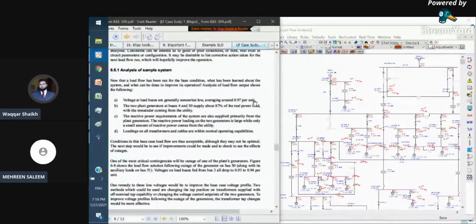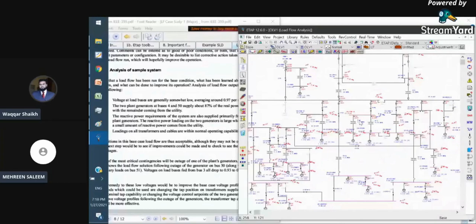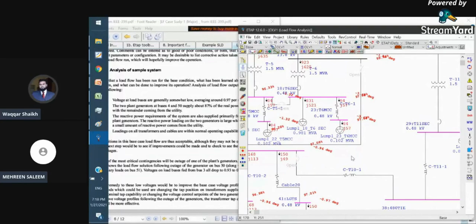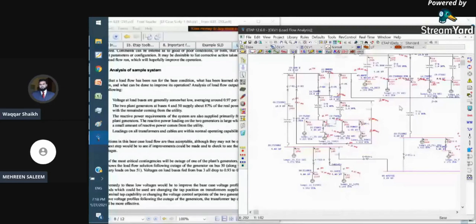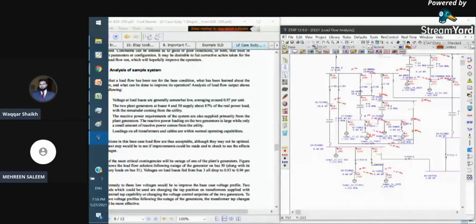So if you see, by running the simulation, you see all the bus voltages, whether medium voltage or low voltage, are 99.7, okay, 99.72%. So you can see all the network buses are above 95%. If they are below 95%, then it would be a problem, and the bus colors would become red or critical alerted buses. So when we run the base case simulation without creating any problem in the network, we found that all the buses are within the 95% criteria of IEEE 399.